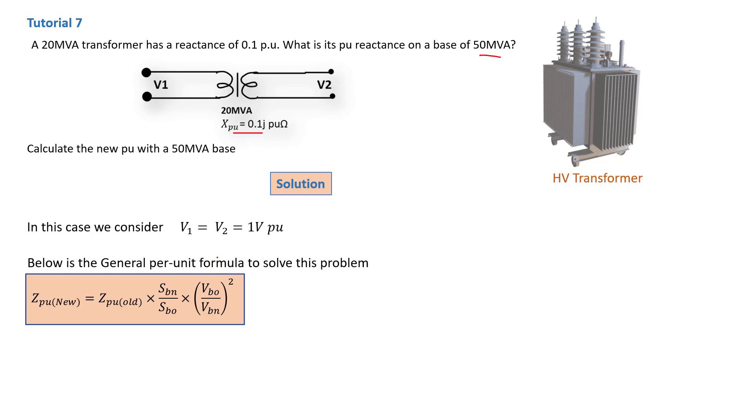So below is the general formula. As you can see, Z per unit new will be equal to Z per unit old. Now Z per unit old, that is 0.1j that is given to us. SBN, that's SB new, and that will be the 50 MVA. And SB old, that is 20 MVA.